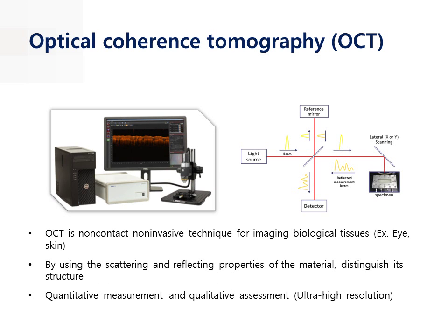In this slide, I will explain the OCT device, its basic principle and properties, and the reason why we selected this device in our research. The left figure is an example of the OCT system, and the other is the principle of OCT. Light from a source is directed onto a partially reflecting mirror and split into a reference beam and a measurement beam. The measurement beam is reflected from the specimen with different time delays according to its internal microstructure.